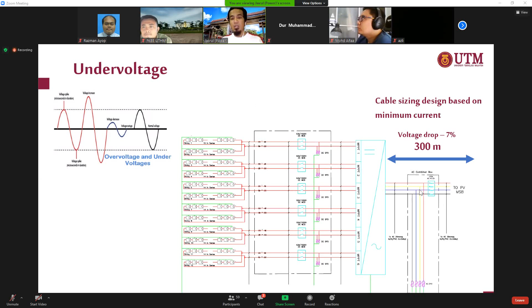So the second is about the over voltage. Okay, for example, let's say this is our distribution system. We have load 1, load 2, load 3, and load 4. Okay, this one is more through simulation because I don't have the actual data. Let's say without the PV farm, this is the voltage pattern that we will obtain. Here from bus 1, we get 1.017, and at the end, bus 4, we might have 0.997. In this case, we can say that all the voltages are within the acceptable limit. If you still remember, plus 10, minus 6, isn't it? In this case, it's only minus 0.003, or in other words, 0.3%. Okay, so this is the range that we have without the PV.